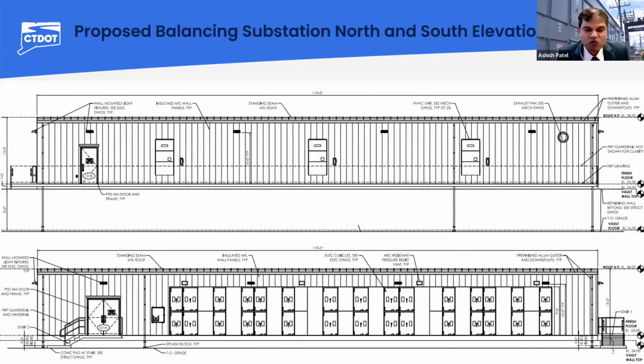This slide shows the elevation view of the new walk-in type balancing substation. It is also called a prefabricated balancing substation enclosure. It will be installed on top of the full walk-in type vault. The fabrication of the entire substation enclosure will take place at the balancing substation manufacturer's factory. After successful testing at the factory, the balancing substation will be delivered to the project site. The contractor will be using a crane to unload the substation from the delivery truck to the substation foundation.